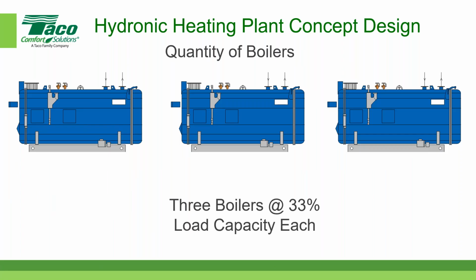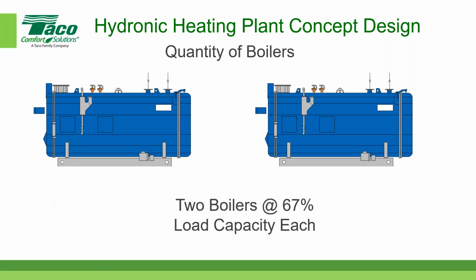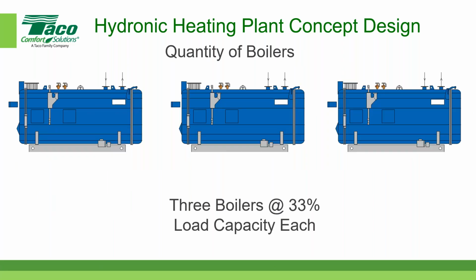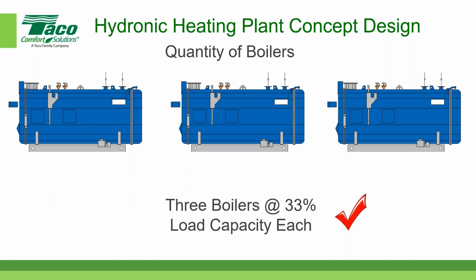With 3 boilers at 33%, if you lose one boiler, you'd have 66%, and that would allow you to heat the building for roughly 75% of the time. Depending on where you are in the country, that might even be higher. 2/3 of the capacity might provide as high as 90% of the heating hours available. And then there's also the possibility of 50% or 33%. My personal choice is the 33%.